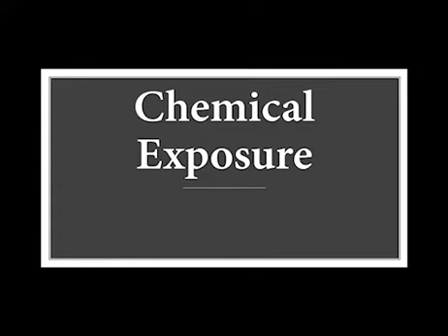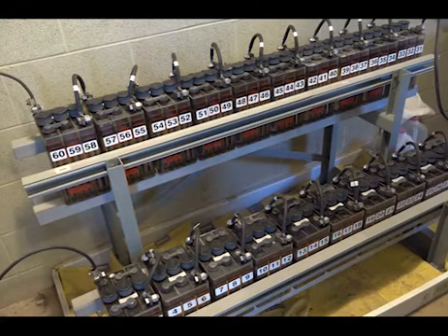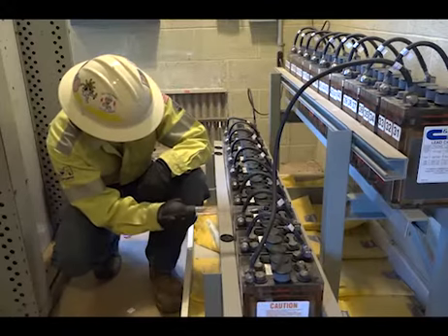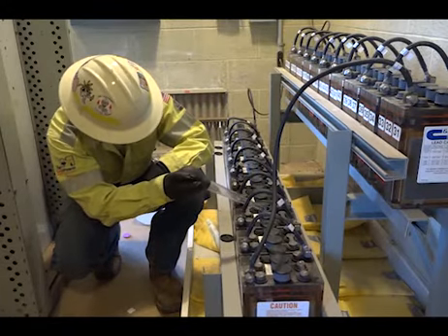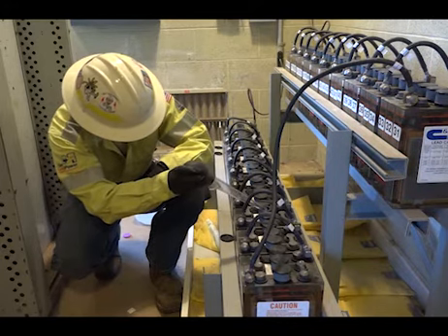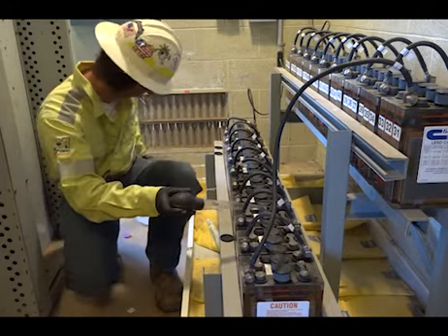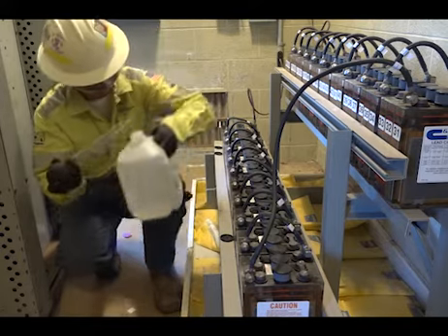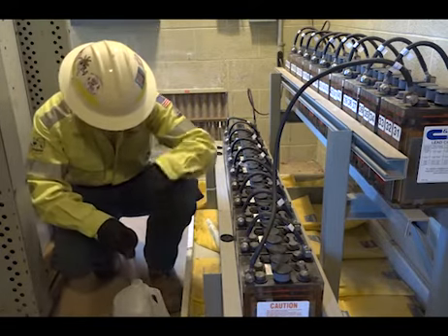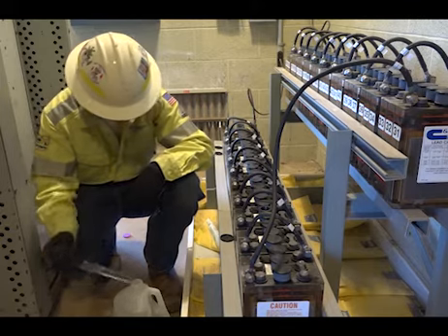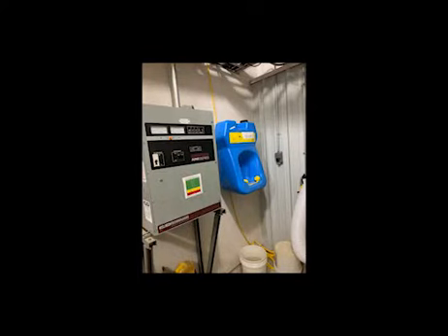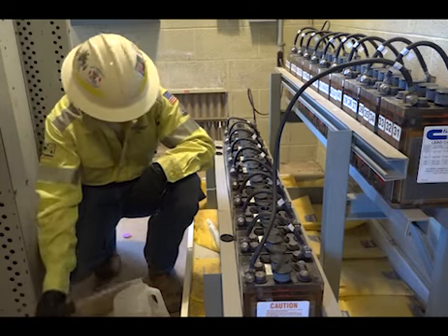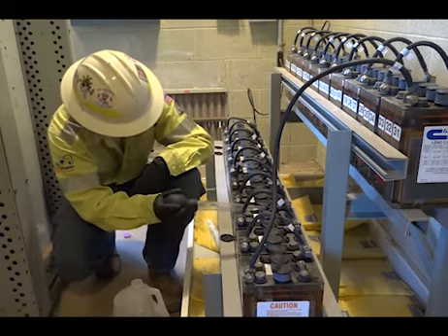Chemical exposure. Lead acid is present in the substation DC batteries. When working near these batteries, use caution and wear proper PPE. When adding water to the batteries, be careful not to splash acid onto your eyes or skin. Should acid get splashed onto your skin or eyes, use the nearest eye wash station located in the control building to rinse off appropriately. If working above batteries, ensure they are covered to prevent causing a fault.